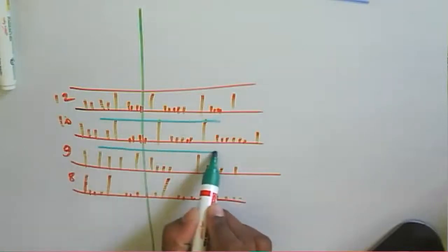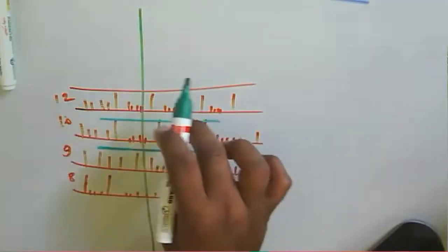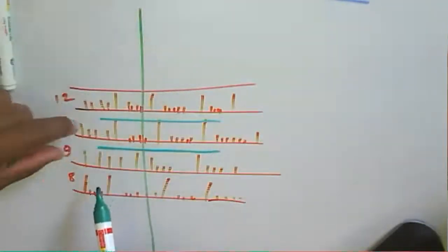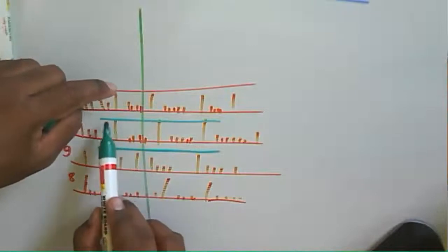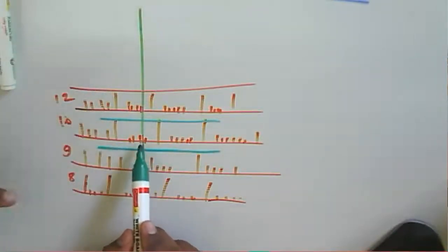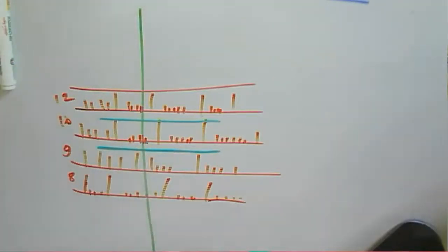In between that vertical line, two lines are there. These two are fixed. When we rotate, it rotates from one scale to another scale, and when it goes up or down it rotates across the different scales. This vertical line and this green line will coincide at one particular scale here, and at that particular point that will be the frequency. So that is the direct method, the dip method.